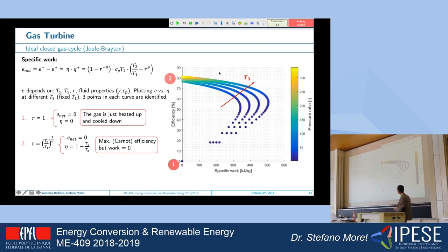because you are actually setting the efficiency up here, and if you do the calculation, you see that the work here is zero. So, what you want to do in a cycle, you can derive this equation to find the maximum. You can derive it over R and put it equal to zero. And you find for each fixed T3, for each maximum temperature, that the maximum amount of work is this point up here. Okay? So when you design a cycle, you want to have a trade-off between the efficiency on the left-hand side and the amount of specific work that you are producing.